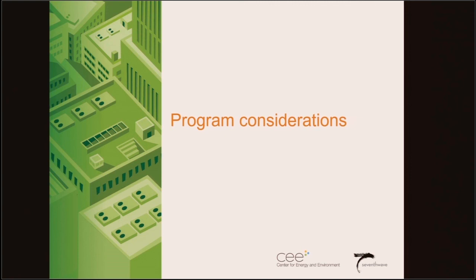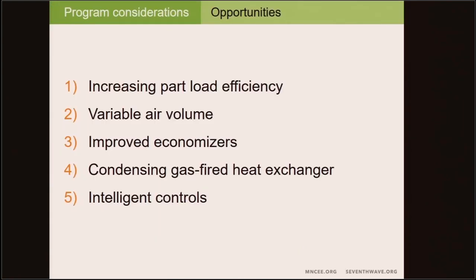All right, thanks, Mark. And to round out the presentation, we'll talk a little bit about some program considerations. Manufacturers are offering new products and features that continually increase the available efficiency options for new RTUs. Although this list isn't comprehensive, it represents some of the larger opportunities for savings. The main trend for increasing RTU energy performance is in increasing its part load efficiency through the use of variable speed and variable capacity components and associated controls. These systems have the added benefit of increased humidity control, which therefore increases occupant comfort as well as energy performance.